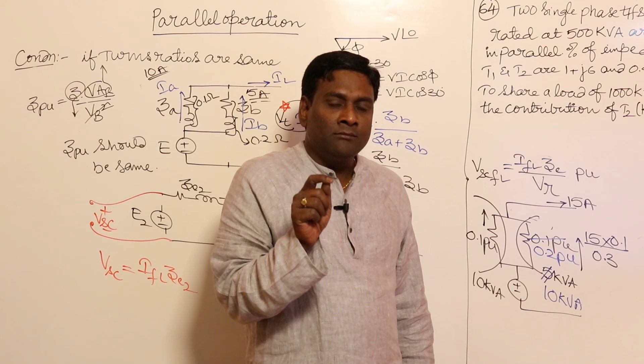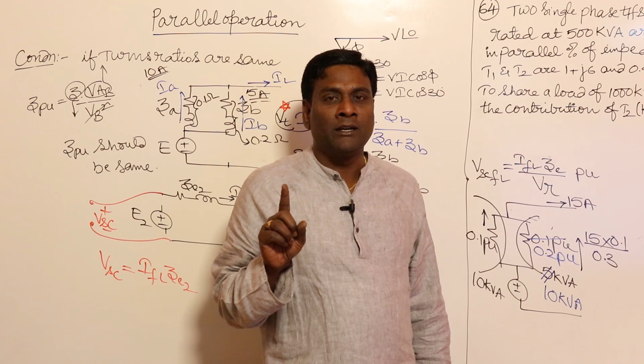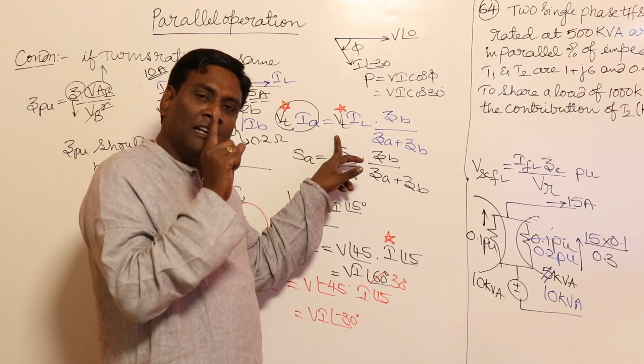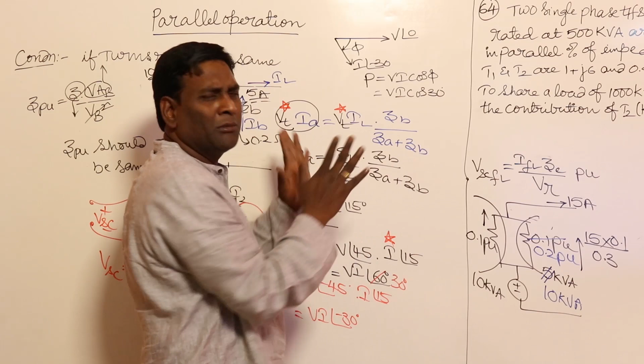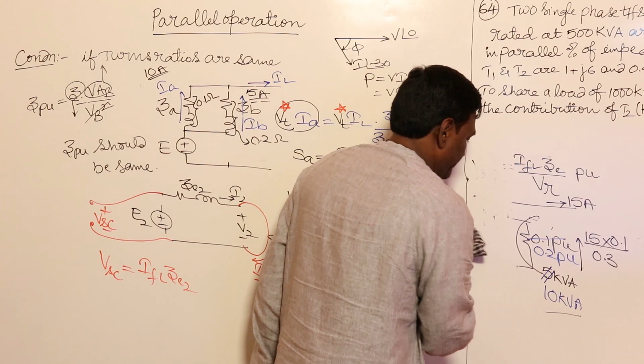So the point here is very simple, remember this. Z per unit should be referred to a common base in parallel operation of transformers while calculating load shared by individual transformers. That is one thing. And the second thing is, you should not make this mistake by following some kind of book. Some people say that if it is lagging you have to keep plus. No, if it is lagging you have to keep minus only, because this is the current division rule. If you remember these two, problems can be solved. Now let us take up two problems.